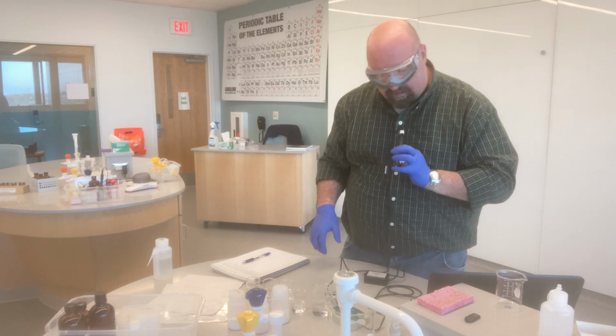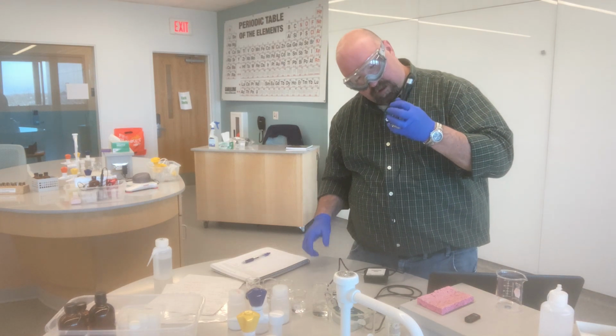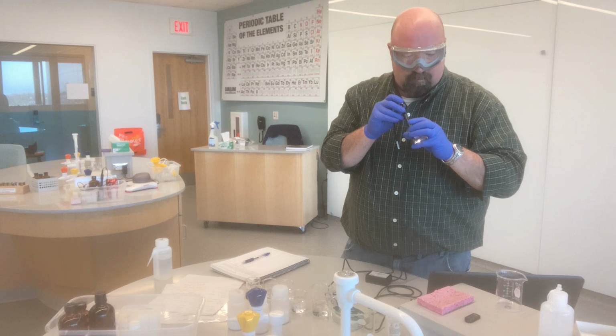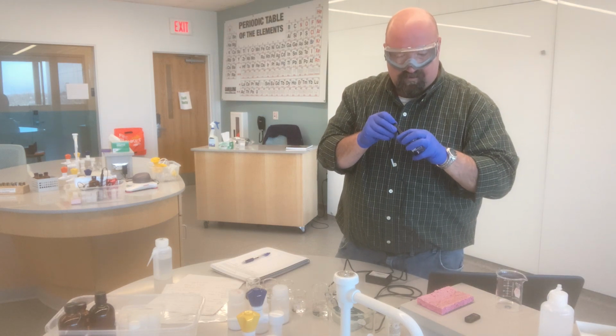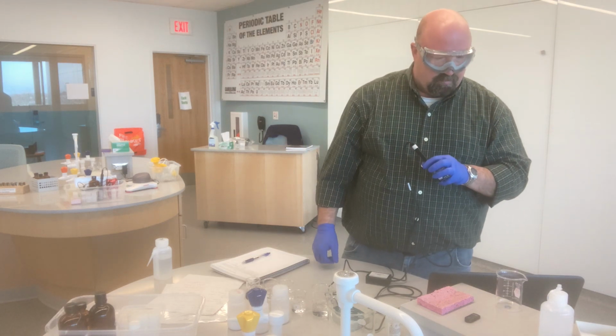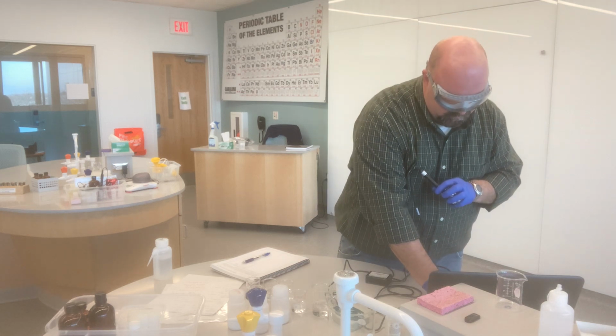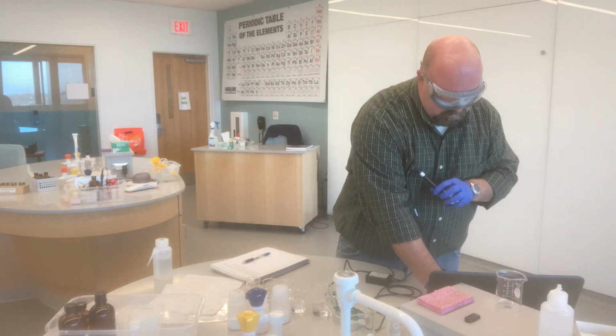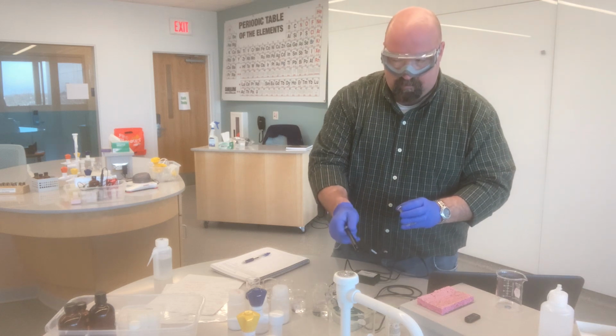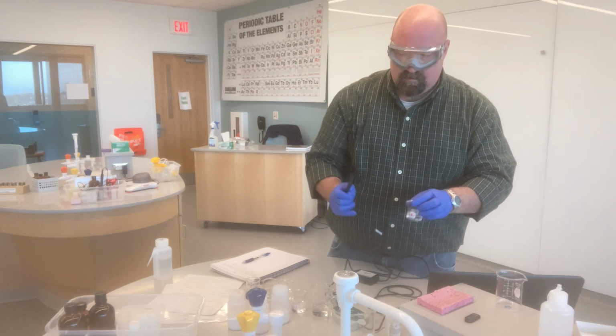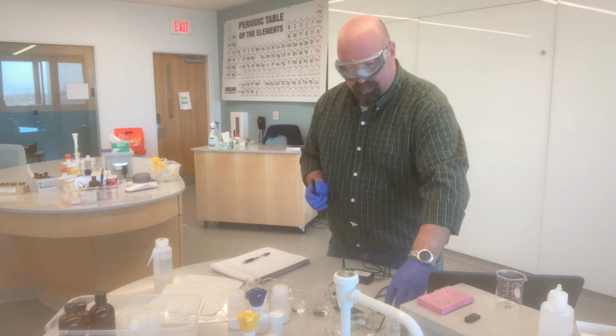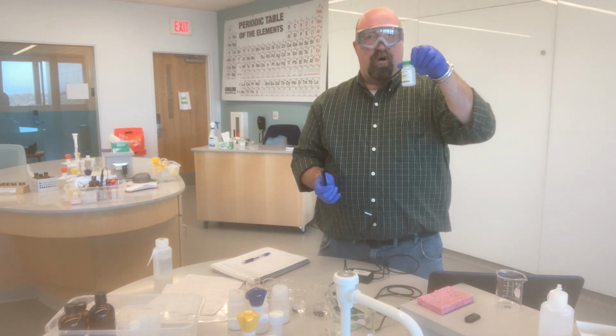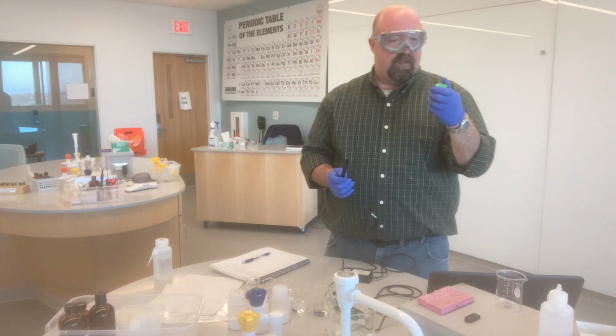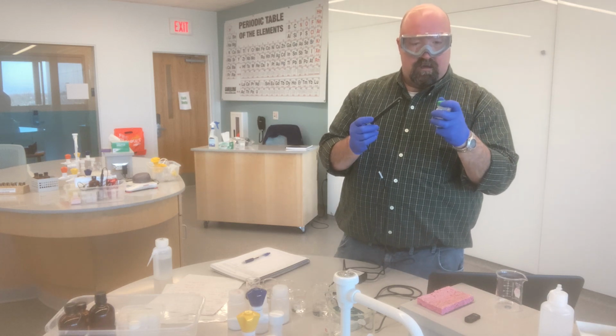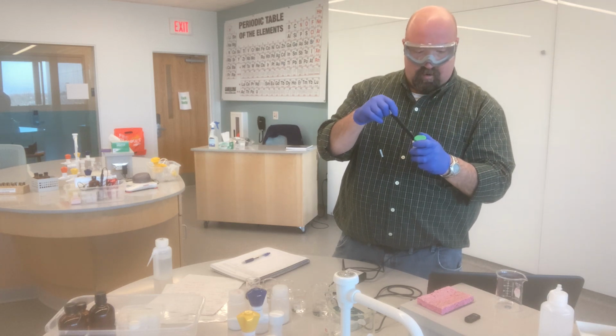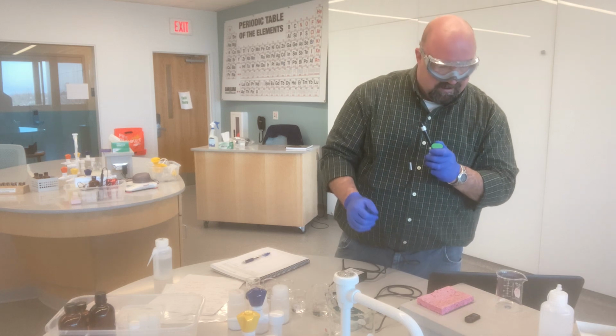And so I stick the probe down in there, again making sure that I am fully immersed. There's not quite enough water in there to fully immerse it, so you'll see what I'm doing is just tilting the beaker a little bit, just to get it deeper on one end to make sure that it is immersed. So there's my 0 point. I just shake the probe off a little bit into my waste beaker. And then we have a 1000 microsiemens per centimeter standard, and I can just stick the probe right down into that standard.